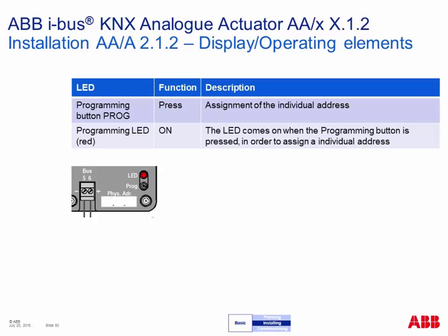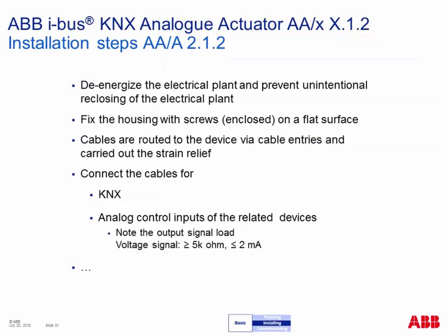So it is a standard KNX device, so we still have our programming button and the LED. Also for testing, you can press the programming button and then we will see the red LED is on or off, showing whether we have KNX bus voltage, yes or no.